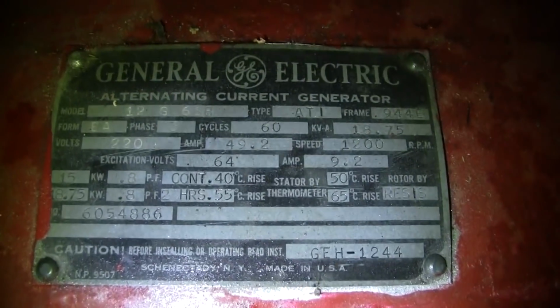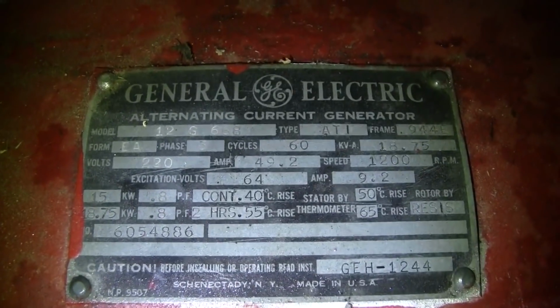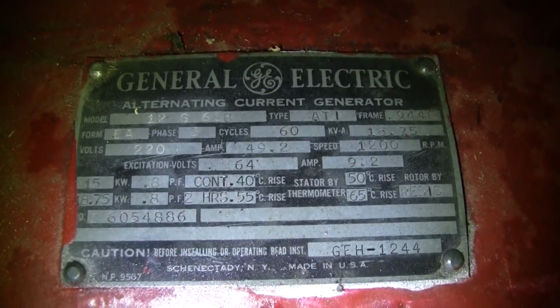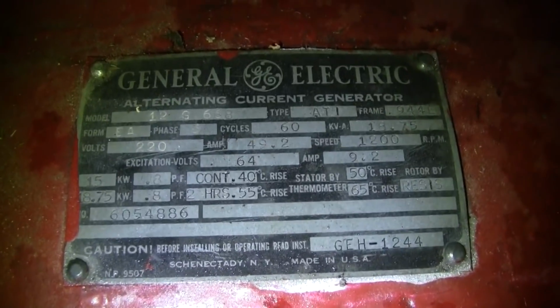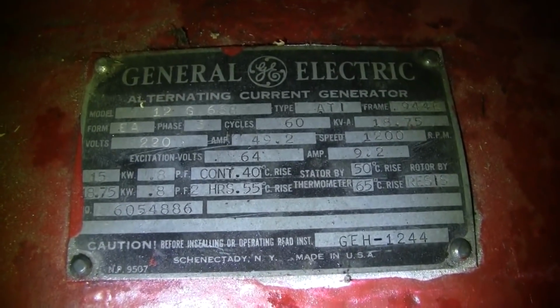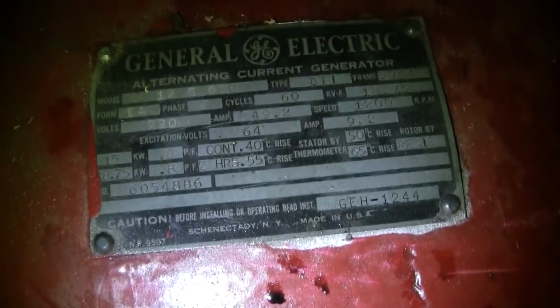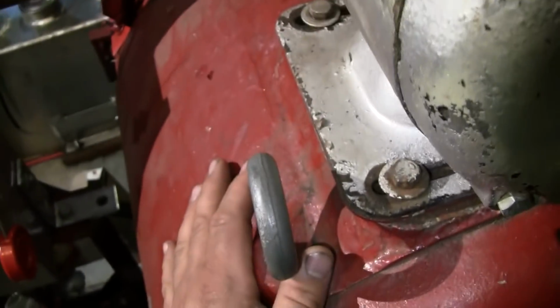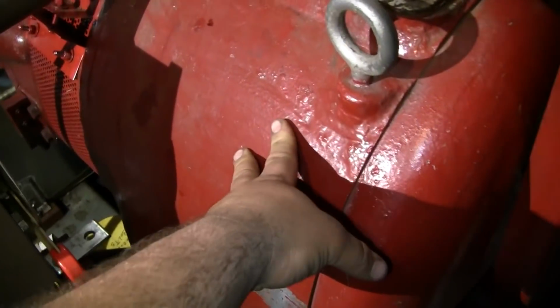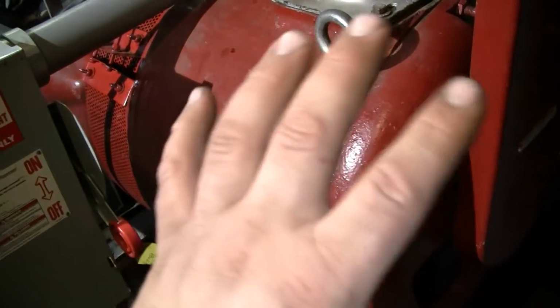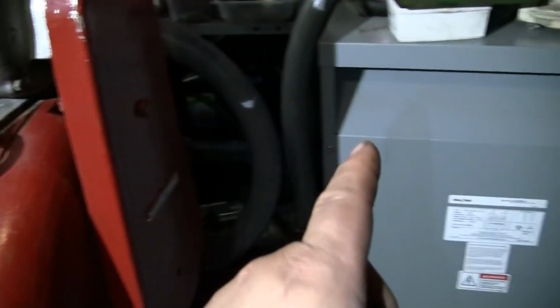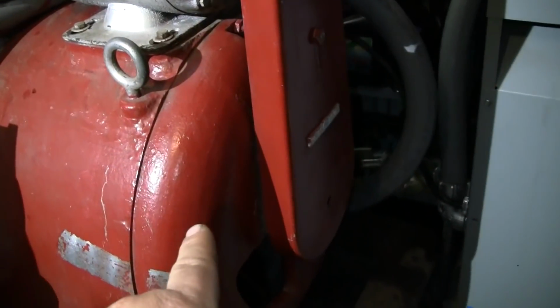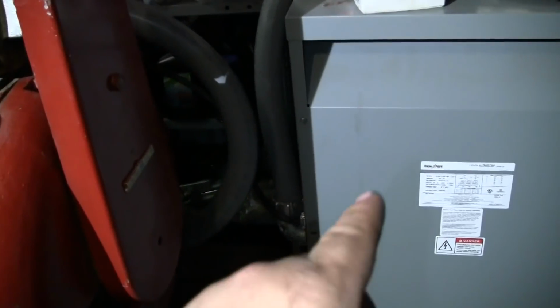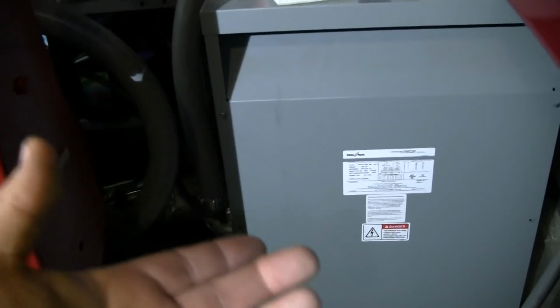Here's our generator information. It is 15 kilowatt continuous at 1200 RPM. Notice the voltage listed is 220, not 110-220 or 220-240 - it's 220. So this generator end was built without a neutral, only 3-phase output. So when the owner had this installed, he got a transformer to take the 220 3-phase and change it over to 120/208 3-phase to allow 120 volt loads to be operated.